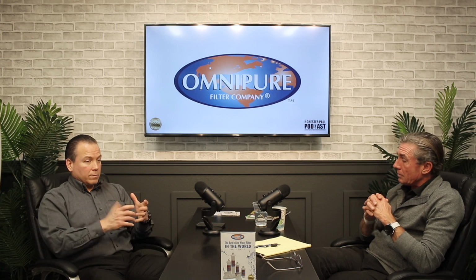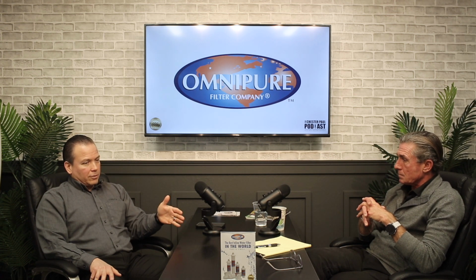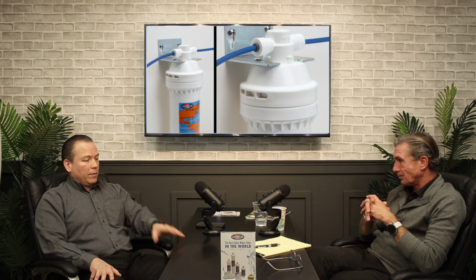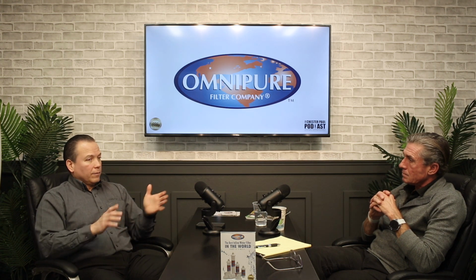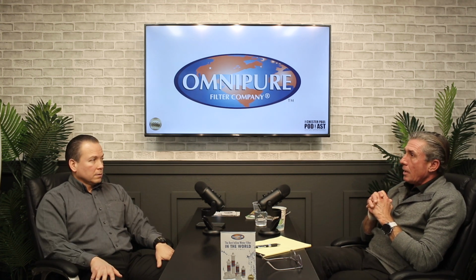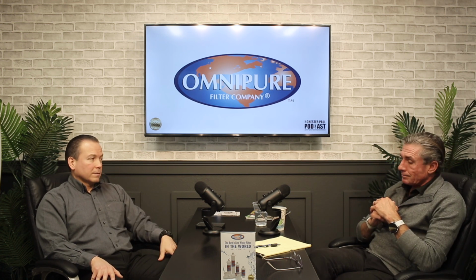For the ELF we have an auto shutoff head and a non-auto shutoff head, and there's a bit of a difference. The non-auto shutoff head only comes in 3/8 female thread or 3/8 quick connect. The auto shutoff head only comes in quick connect, 1/4 and 3/8. So on the valve head, which is the auto shutoff, there is no female pipe thread option. The 3/8 is more common for the flow rate and for most applications in food service and other industries. It fits the flow rate of a 1.5 to 2 gallon a minute application as well.